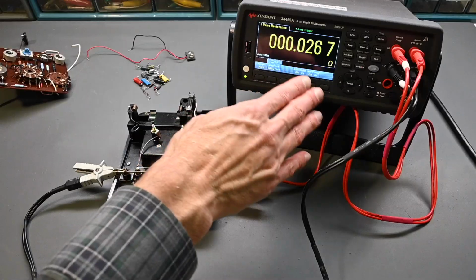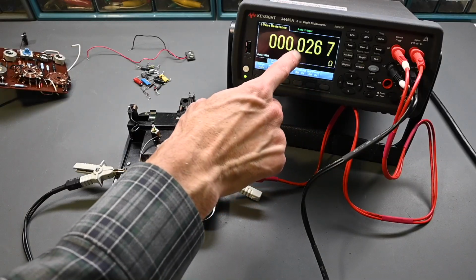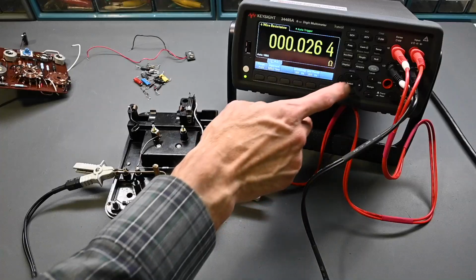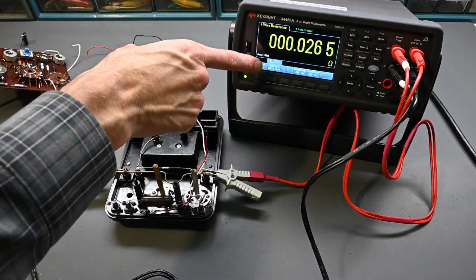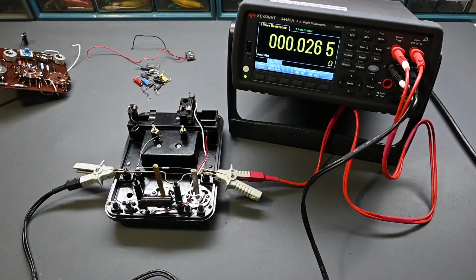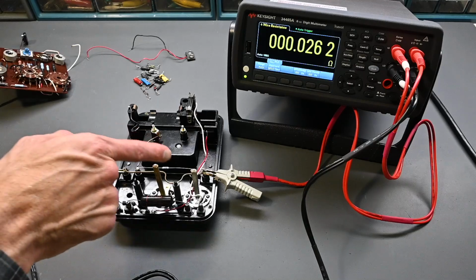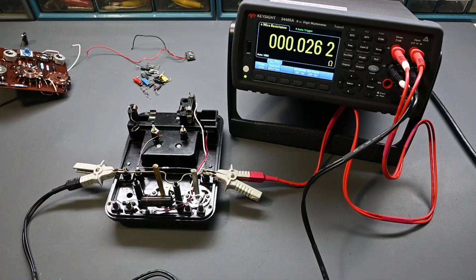So that's supposed to be ideally 0.025, and we're at 0.026 and some change. And if I change the power line cycles, it was 10 power line cycles, now that's 100 power line cycles. So the readings slow down, but they'll stabilize a little bit more. And you can see it's very close to what it should be. So again, 0.025 ohms or 25 milliohms, and we're getting 26.3 milliohms. So it looks like this shunt is in good condition, no problems with that. But I just wanted to show you an alternate way to measure very low values of resistance.